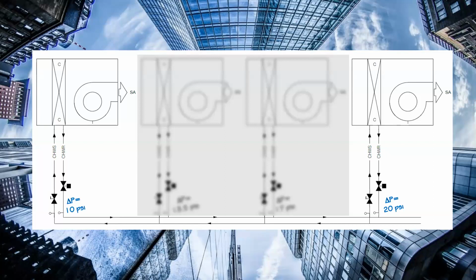So that far zone, 1 psi is now being seen across that balancing valve. So we have less than 4 pounds on the coil, but for the conversation's sake, we'll say that it's still 4. And that means that our control valve is now taking up that additional pound of pressure. It's a slight overpressurization on the control valve, but nothing that can't be overcome. We still have pretty good valve authority, and we have pretty good control of that zone.